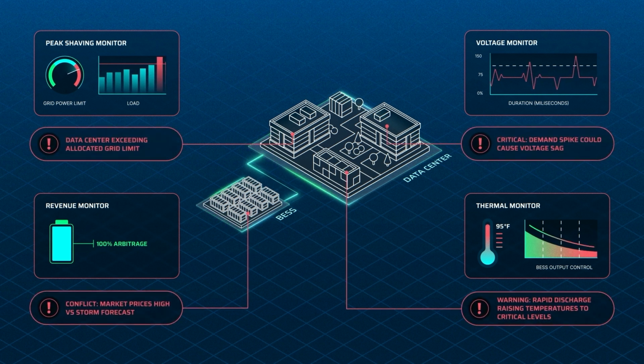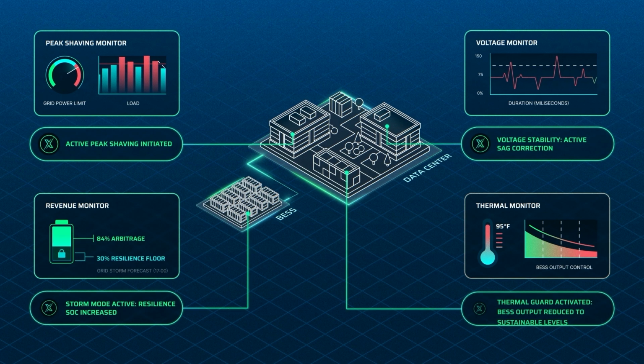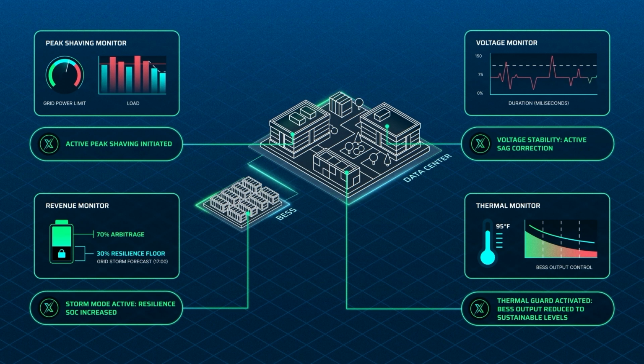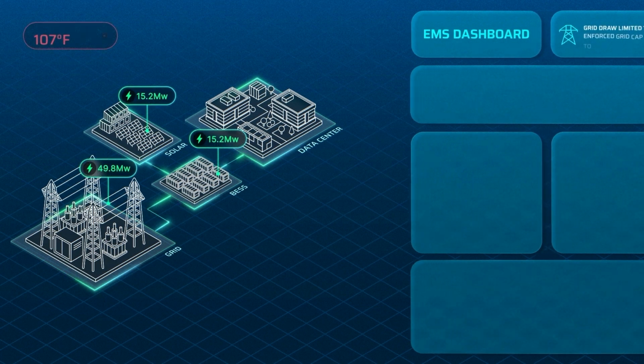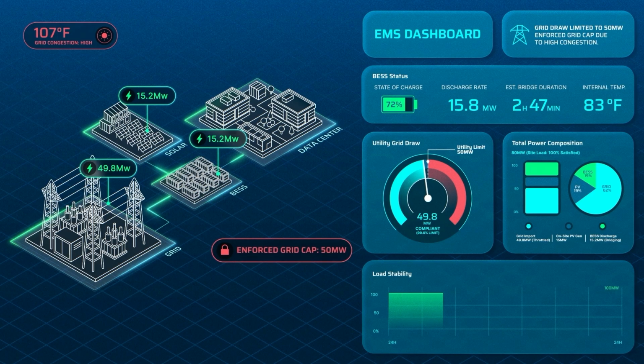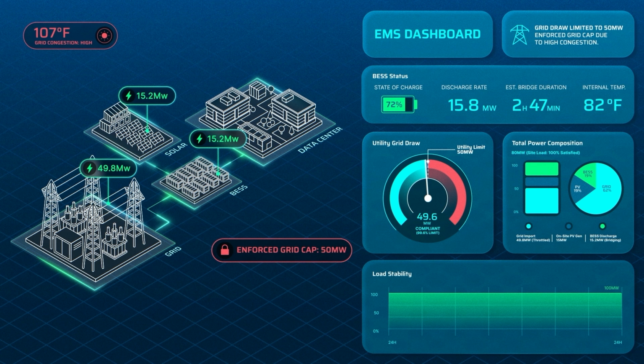Managing two distinct asset classes at one site creates a level of complexity that basic controllers simply can't handle effectively. Without intelligent orchestration, your asset and your battery can actually end up competing for the same limited inverter capacity. FlexGen's hybrid OS serves as the site's digital brain, providing the precise, real-time coordination needed to navigate complex operational hurdles. For example, if the utility dictates you cannot exceed a 50 megawatt limit on a particularly hot day, hybrid OS intelligently throttles on-site generation while using the battery to bridge the gap. This ensures the data center stays at 100% capacity without ever violating the grid's cap.